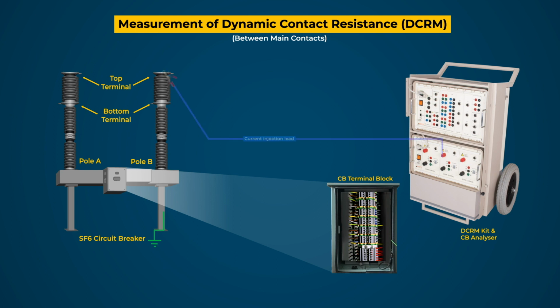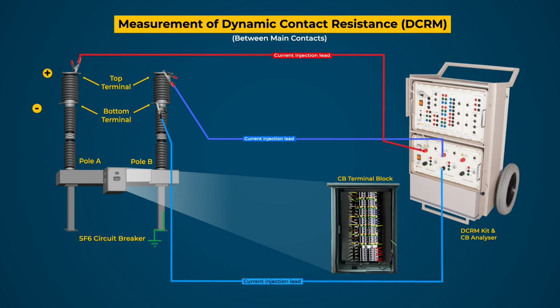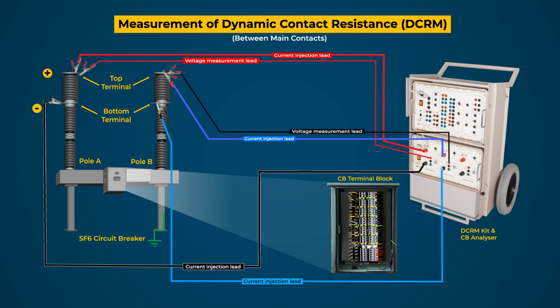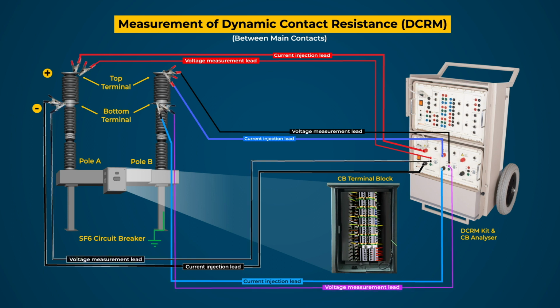Connect the positive current lead of the DCRM kit to the top terminal of the breaker and connect the negative current lead of the DCRM kit to the bottom terminal of the breaker. Now similarly connect the positive voltage lead of the DCRM kit to the top terminal of the breaker and connect the negative voltage lead of the DCRM kit to the bottom terminal of the breaker.